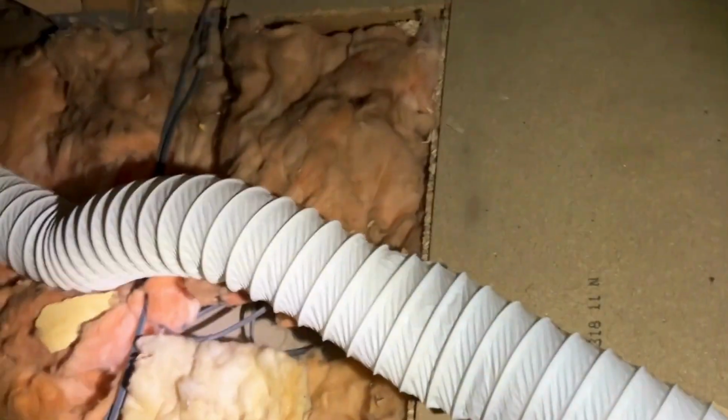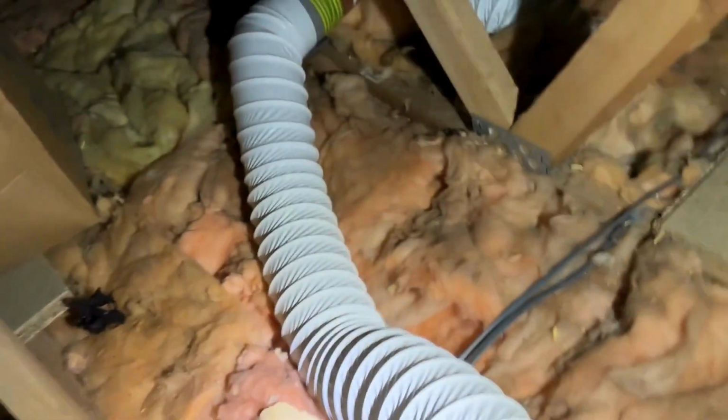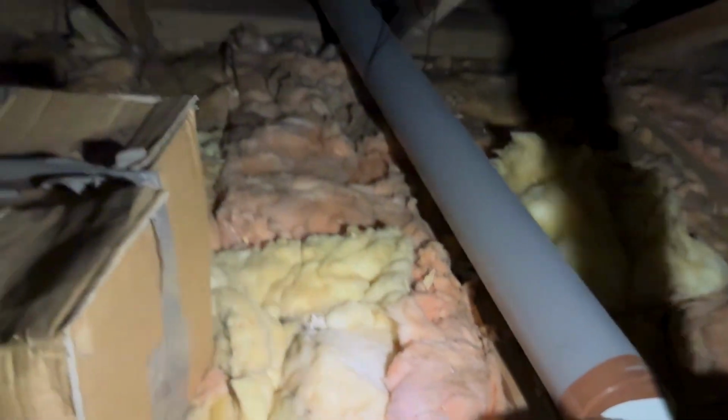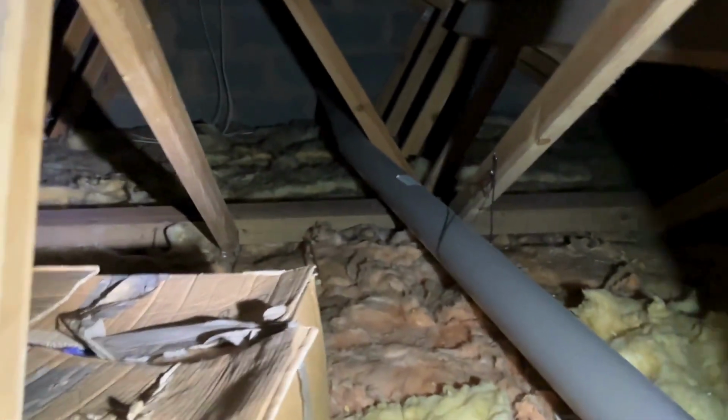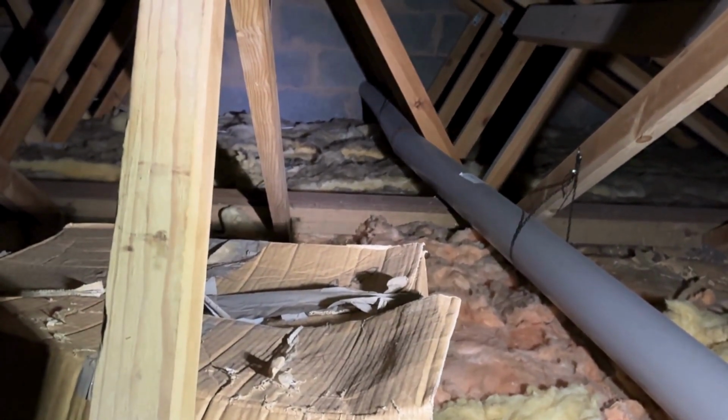In this final example, this is one that is ducted to outside air, but it's probably got the record, from what I've seen anyway, of the longest run of uninsulated ducting across the roof space, joins from the kitchen fan into the bathroom fan, and then along this, looks more just like a pipe that's not been designed for this, going out through a wall vent. And in this case, the ideal alternative would be to either go directly up to the shortest route through a vented roof tile if it's not possible to be going out through the walls.